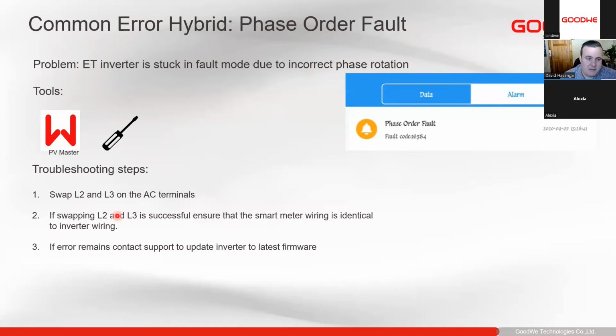So normally to resolve that, we just switch L2 and L3 on the AC terminals. It's always advised to do this on the utility side as far as possible, under the main incoming breaker from the utility. That way it changes everything on the smart meter as well, because you'll see next in our meter fault finding steps, sometimes fixing the phase order fault creates a smart meter fault, because we're swapping the phases on the inverter. We need to then swap it under the smart meter and swap the CTs around to the correct phases as well. That's just one thing to keep in mind when you do have this problem, that you need to swap everything, as well as the CTs and the phases under the smart meter.